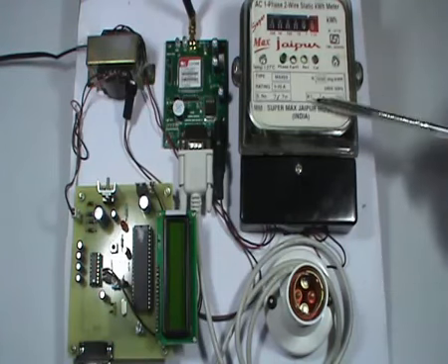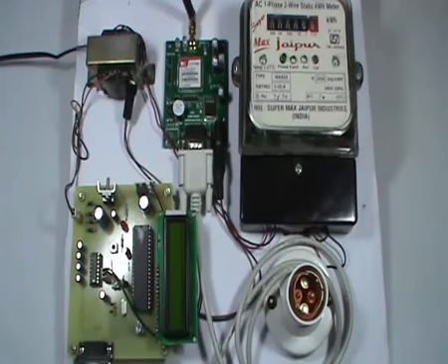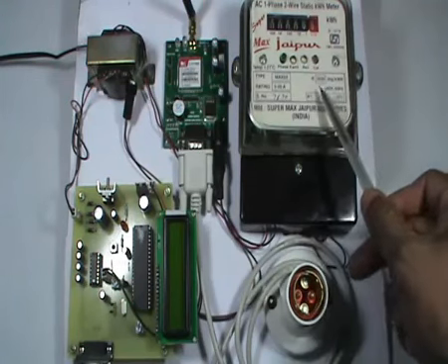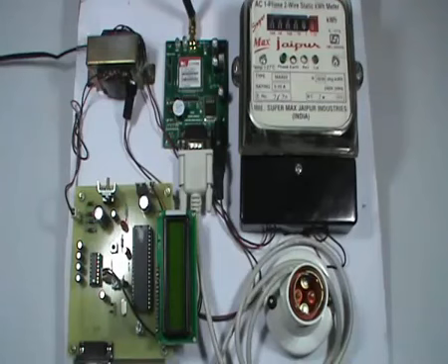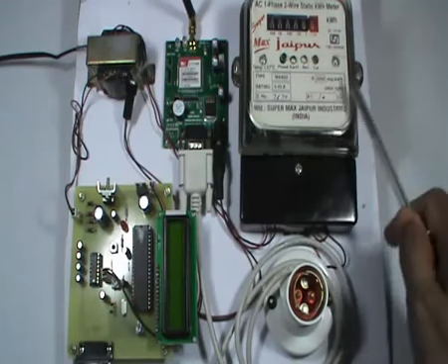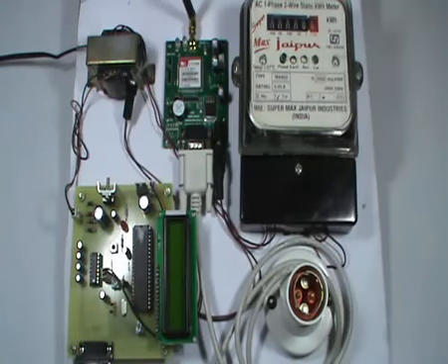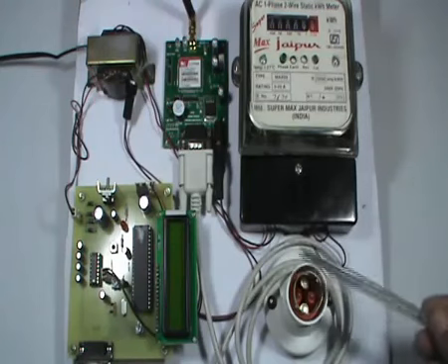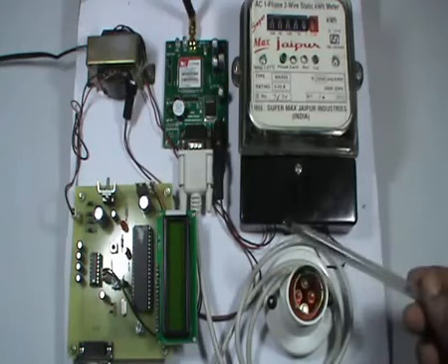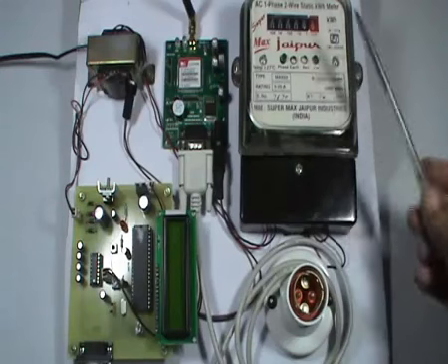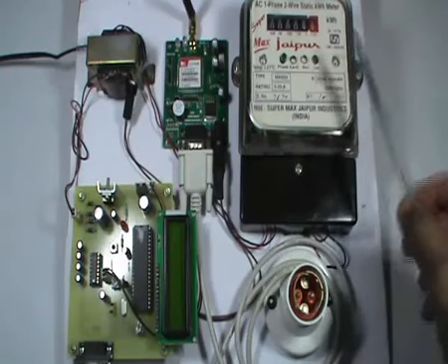We have an energy meter, and the energy meter, as we see, it has got 3200 impressions. That means 3200 blinking of this LED for 1 unit. 1 unit means 1 kilowatt hour. 1 kilowatt hour is 1 unit. This is a single phase meter. Then we have a load here.